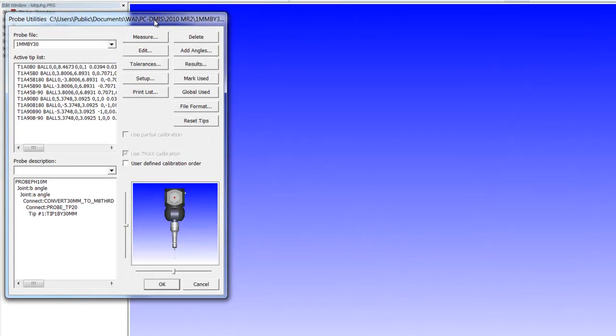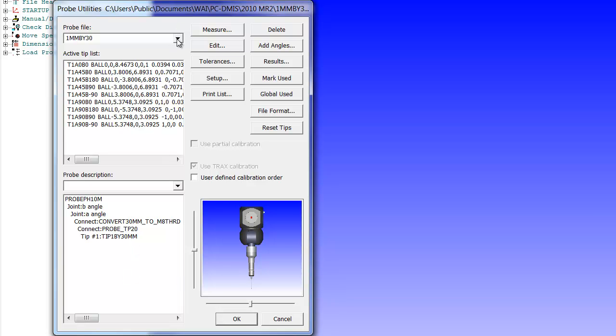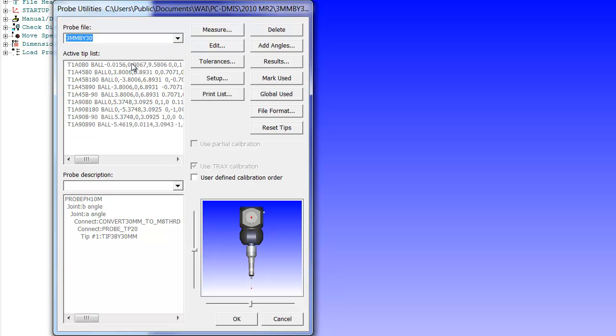When we first start the process, the first thing it does is it opens up the probe utilities window. This utility is used to qualify all your different probes and one of the nice things is it always opens up the very last probe that you used. If you happen to be using a different kind of stylus, you can always open up the previous probe files that you've done, pick it and continue on.